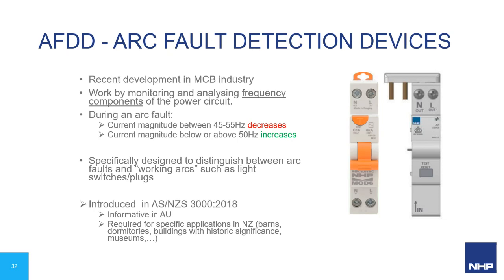The last one I wanted to talk about was AFDD, which is relatively new in the miniature circuit breaker world. These are basically a monitor for analyzing frequency components of the power circuit. During an arc fault, your current magnitude in that main frequency area decreases, and your current magnitude outside of that increases. So it's always doing this analysis, and it's designed specifically to distinguish between arc faults and working arcs, such as light switches and plugs. If you play with those, you can get a little spark in there. It was introduced into AS3000 as informative in Australia, so it's only for information, just saying that they exist basically. And in New Zealand, it was brought in for specific applications: barns, dormitories, buildings with historical significance, museums, where you want to reduce the likelihood of a fire.